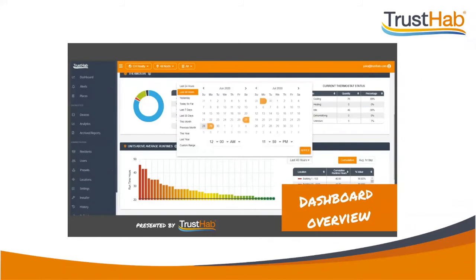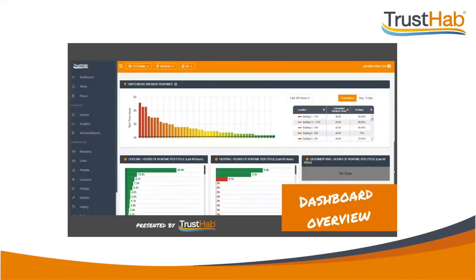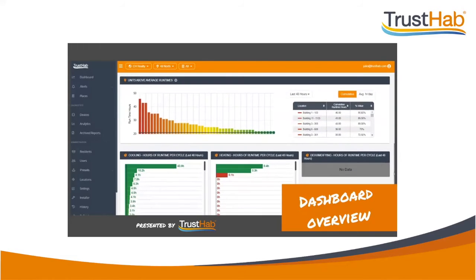There are also widgets dedicated to visualizing the cycle times your HVACs are averaging. Anything less than 15 minutes or more than 45 minutes is usually cause for concern, but you can again easily see which units are blowing that average out of the water. Those outliers usually warrant immediate attention to mitigate further lost energy and HVAC wear and tear.